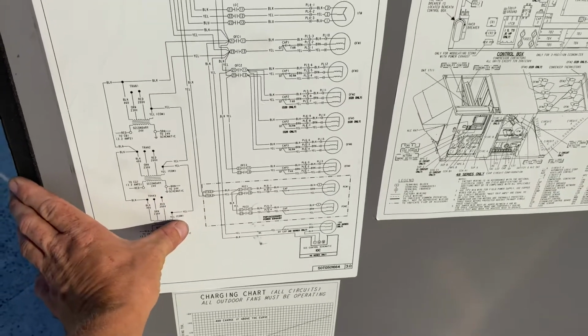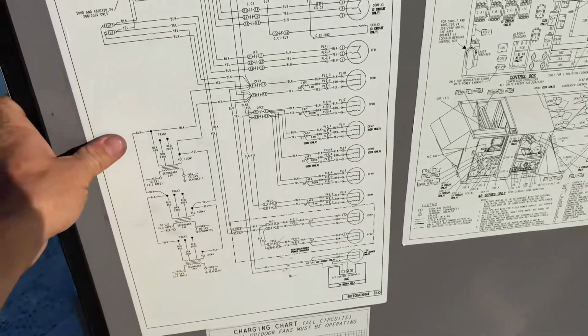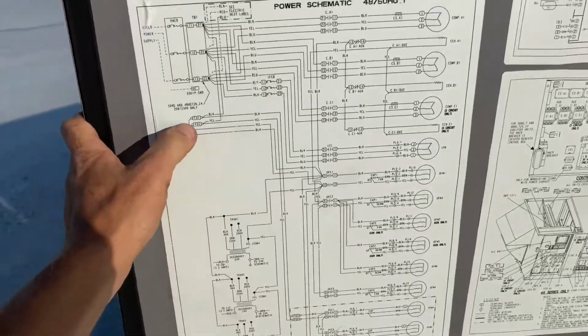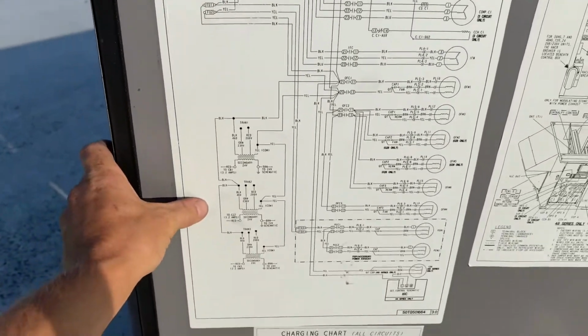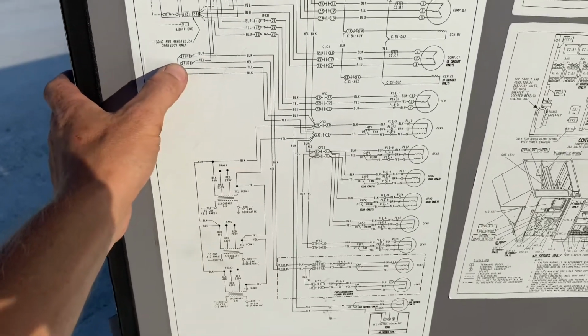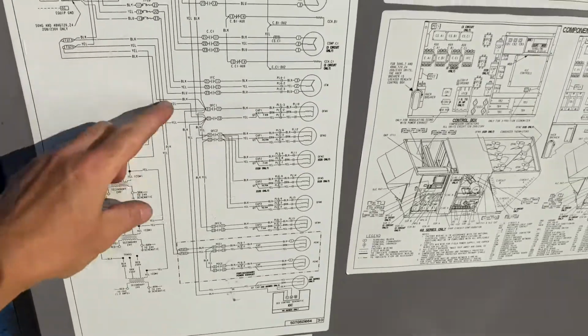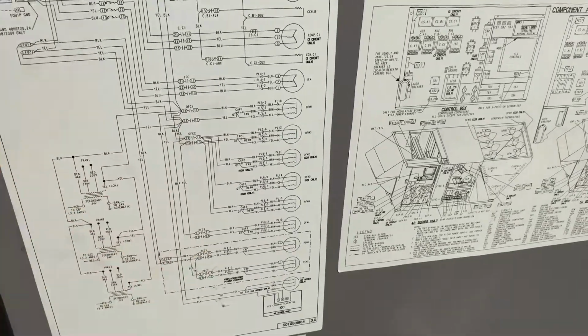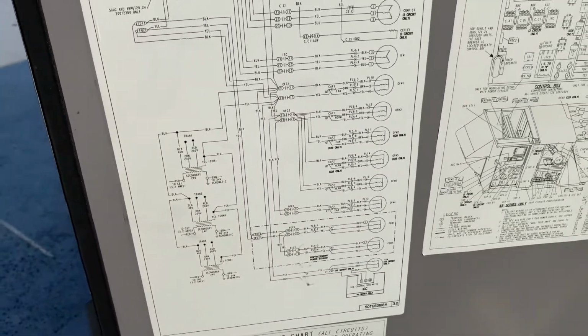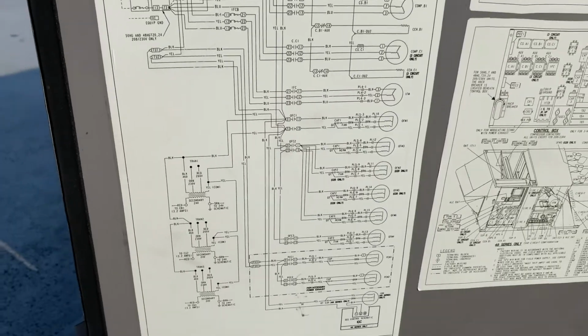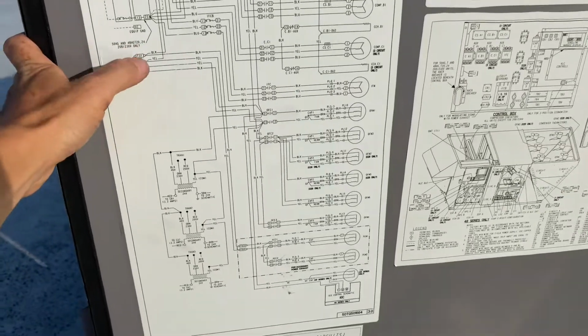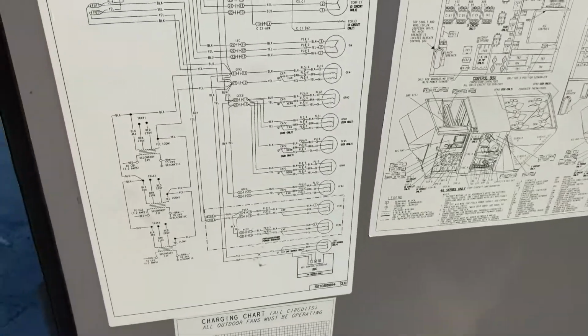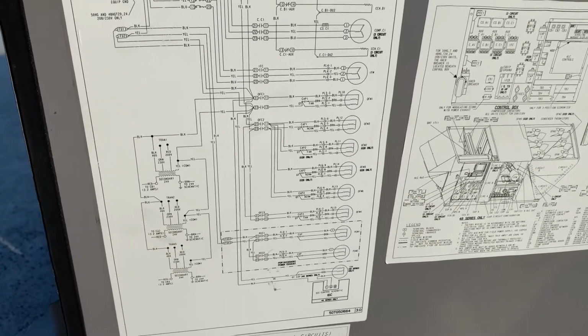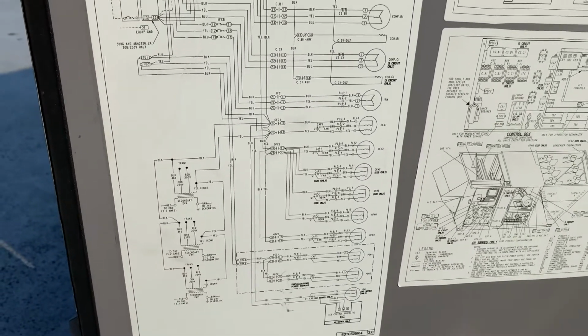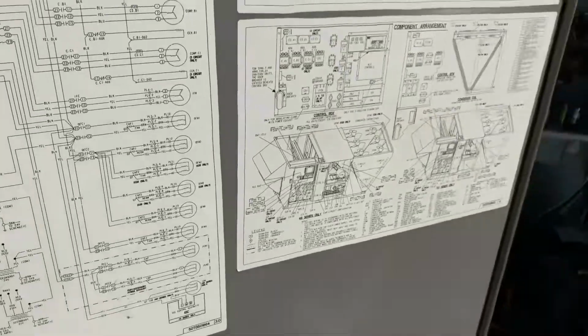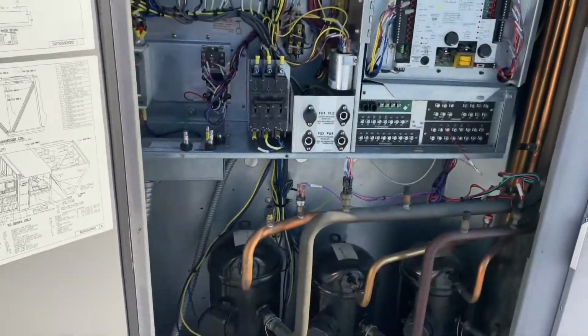Possibly an issue with the power exhaust fans, grounded out. Fuse 2, as well as feeding the transformers, also feeds the common side for all the condenser fans. So it could be an issue with one solo condenser fan causing that fuse to pop, which then killed everything. So what I'm going to have to do is go through the process of elimination, seeing if there's an issue with one of the fans.